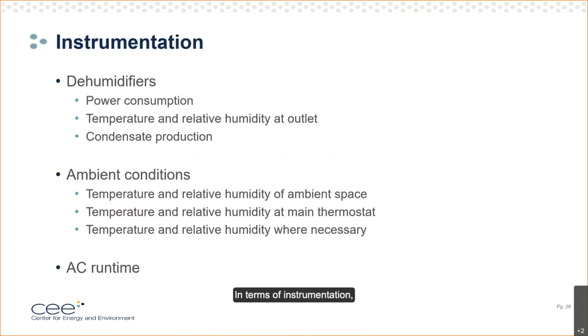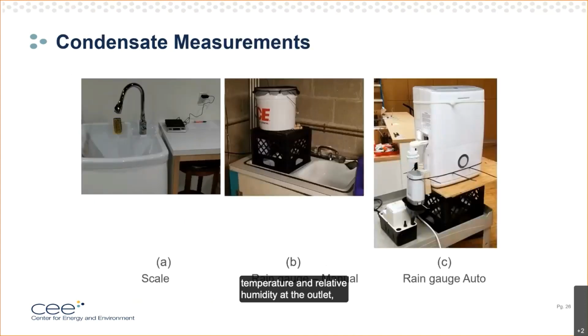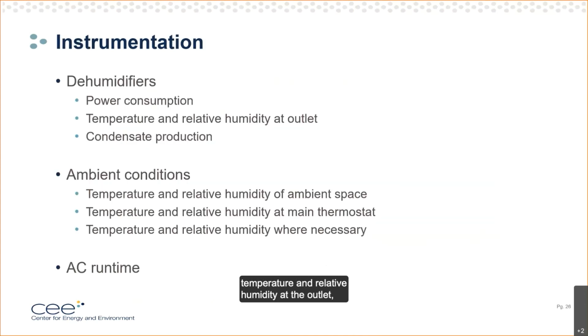In terms of instrumentation, each dehumidifier was outfitted with instruments to measure continuous power consumption, temperature, and relative humidity at the outlet, and condensate production continuously throughout the season. We also put sensors in to measure ambient conditions, temperature and relative humidity in the space being dehumidified at the main thermostat, and in other locations where necessary.